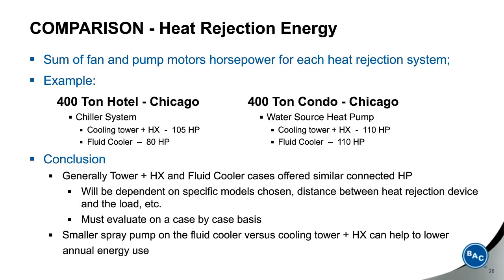At what low ambient temperature can the cooling tower run effectively without any implementation of winterized techniques? Well, certainly any time you operate a cooling tower in sub-freezing weather, you should follow proper operating procedures. There was an excellent article, actually ASHRAE Article of the Year, by my good friend Paul Lindahl of SPX Cooling Technologies that reviewed the winter operation characteristics of cooling towers. And the basic conclusion was that following these proper procedures, you shouldn't have any problem at all.